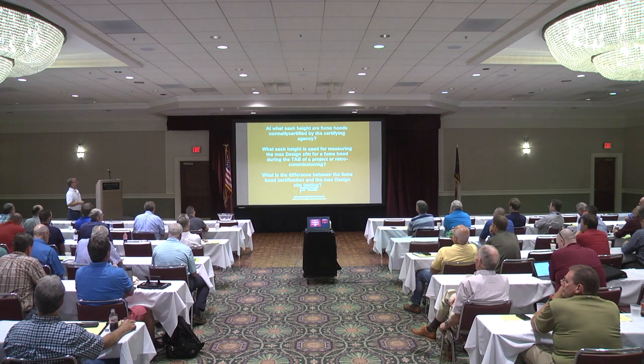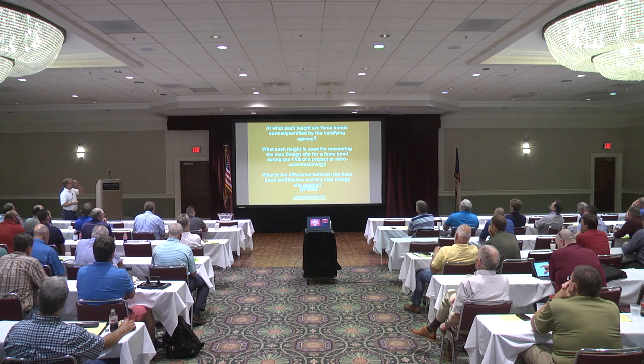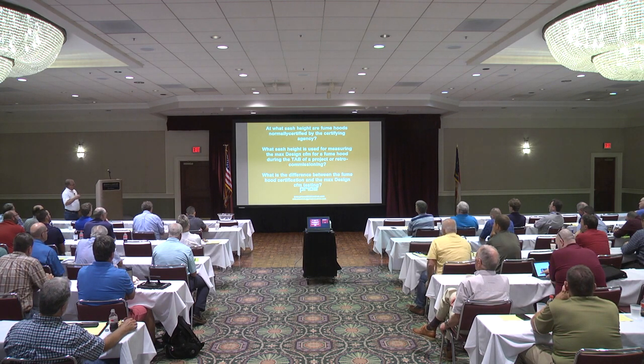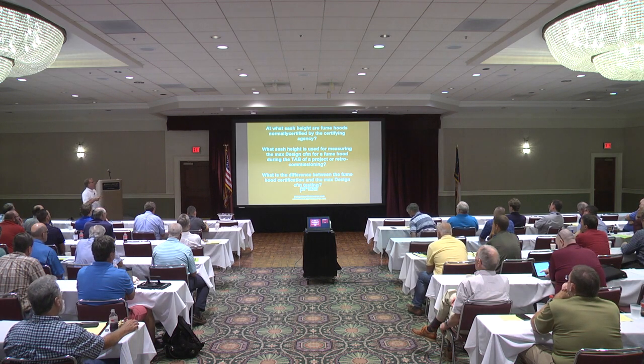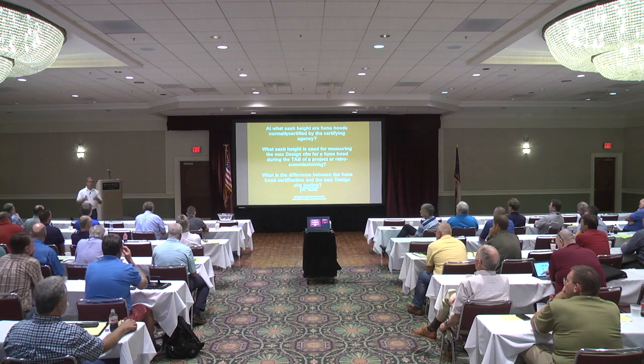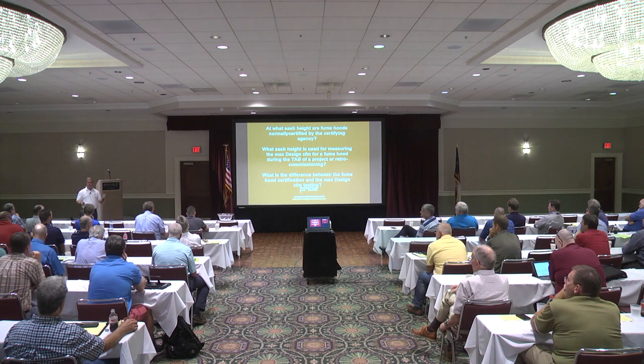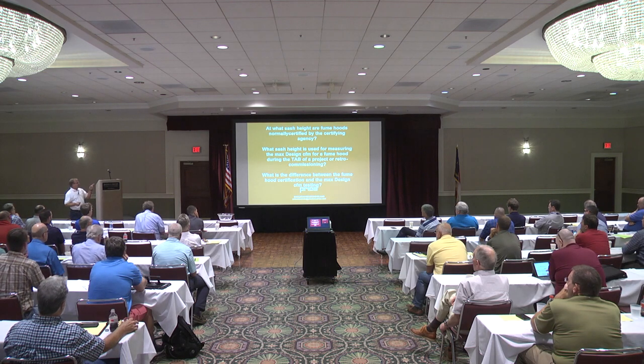All right, a couple of questions I've come up with. I see this all the time in labs. At what sash height are fume hoods normally certified by a certifying agency, called a third party? Maybe y'all do some third party. What would be the standard answer? 18 inches. What sash height is used for measuring the maximum design CFM for a fume hood during the TAB of a project or retrocommissioning?